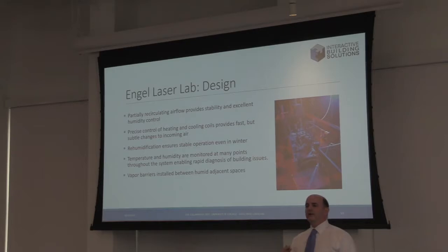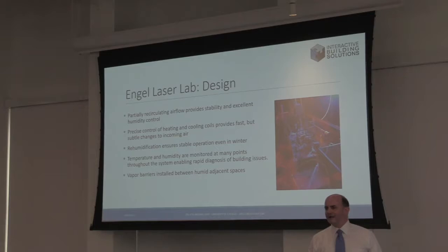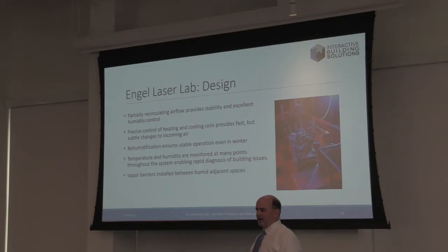Where in the lab do you put the laser table? How do you make this like an air curtain? How do you ensure that you are as stable as possible at the laser table while maintaining a clean environment? Do you push the air down on the table, or do you push it down on the sides and suck it up over the table? What's the right way to do this? So there are a lot of airflow considerations. There are a lot of issues of resonance to make sure your ducts aren't going to vibrate, because you can hear things down to about 30, 40 hertz, but my table resonates at 10 hertz in one direction and about 2 hertz in the other. And so any little bit of rumbling will affect these types of...